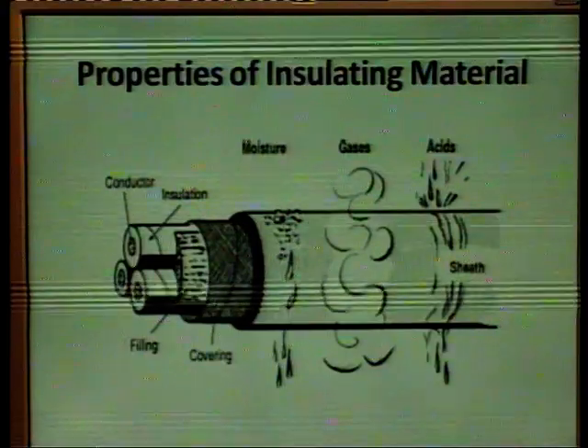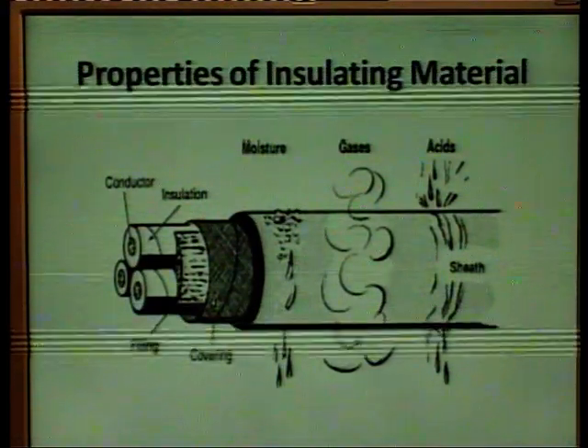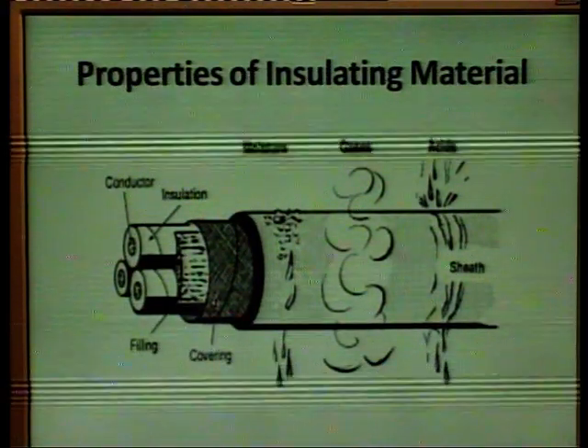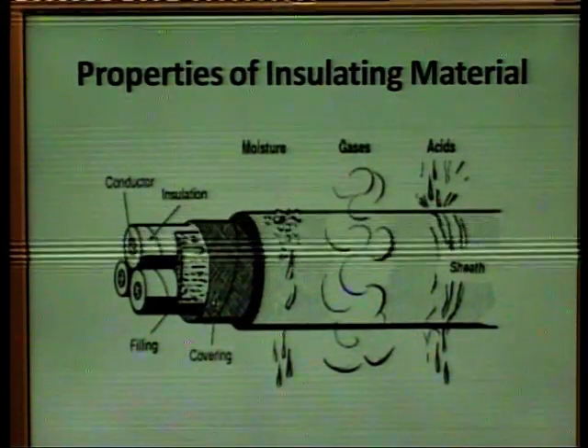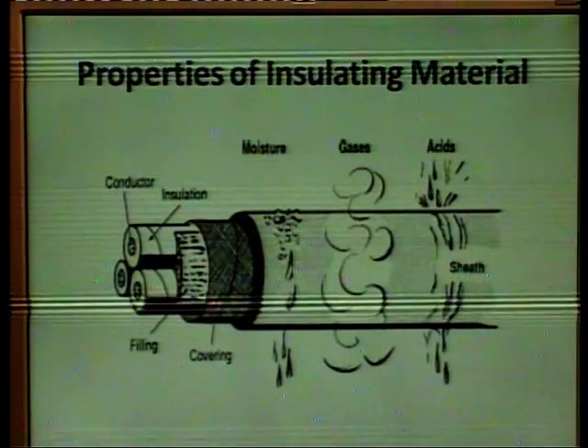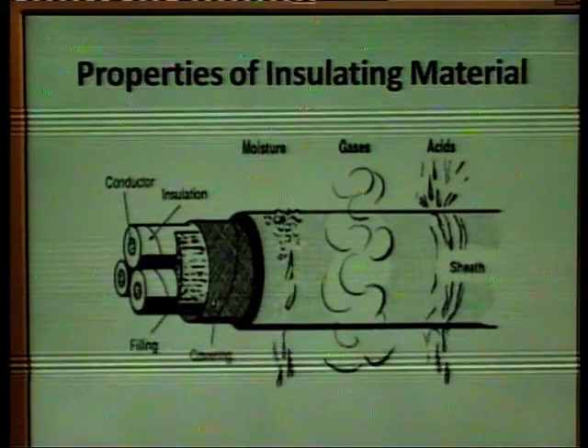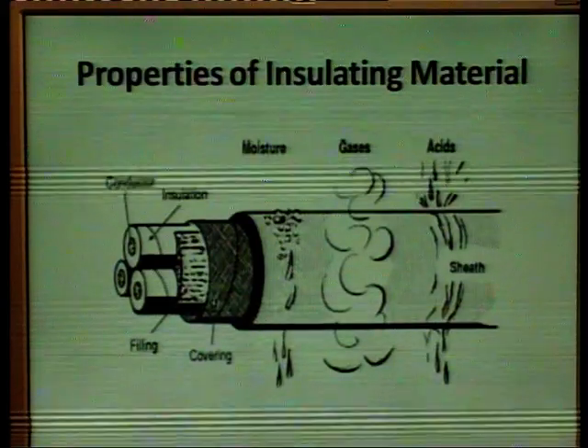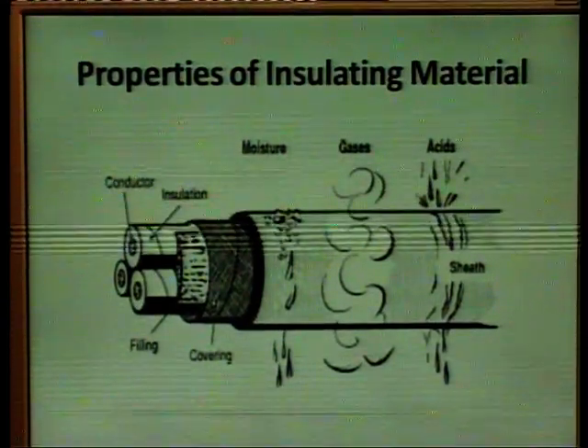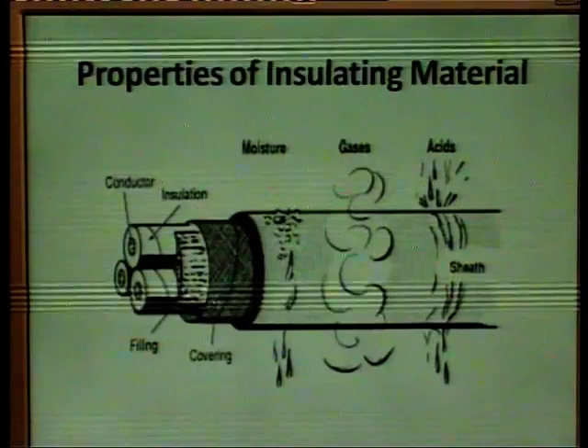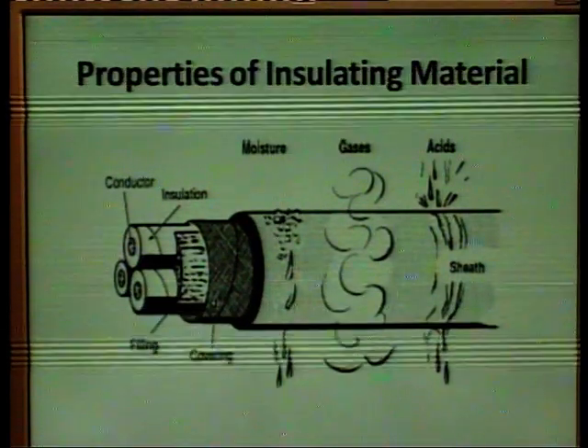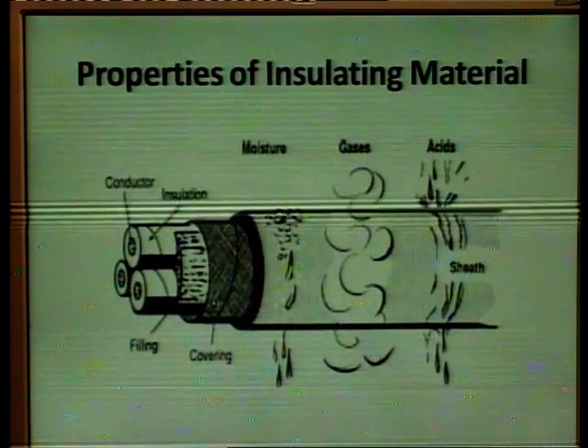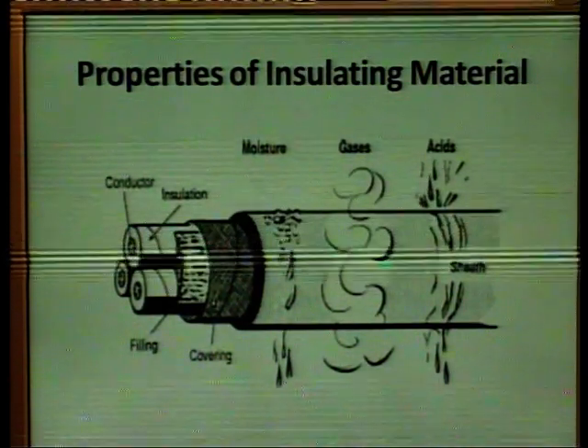So these are the properties of the insulating materials. It should be able to withstand the moisture. It should be able to withstand the gases, the outer sheath. It should be capable of dealing with the acids, because when we bury the cables under the ground, all these are present. The acids, moisture and gases should be there. So the insulating material should have the property to withstand all these.